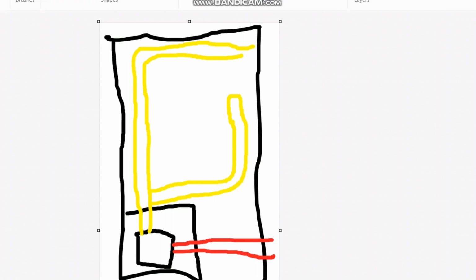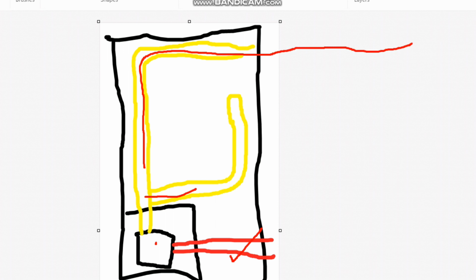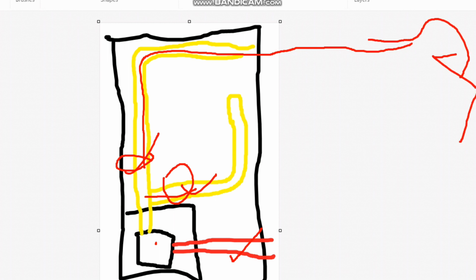Normally in the project site, from the VAV or from the FCU, we will not get proper air distribution from the left or right side. For example, like you see here, we have the air handling unit which supplies the air through this duct to this VAV. From this VAV, I have taken two branches, one here and one this side, and these branches are further going to the other parts of the building. In this case we don't have equally divided branches. Here the airflow rate is, for example, 200 liters per second, and here it is 500 liters per second. So this is going further to different parts of the building, supplying the air to different parts.